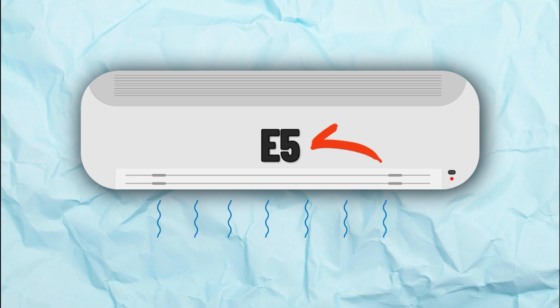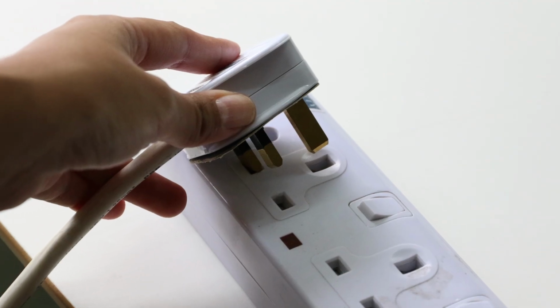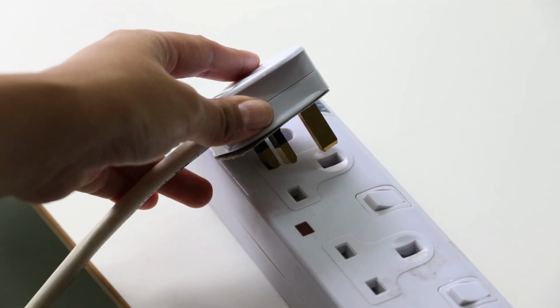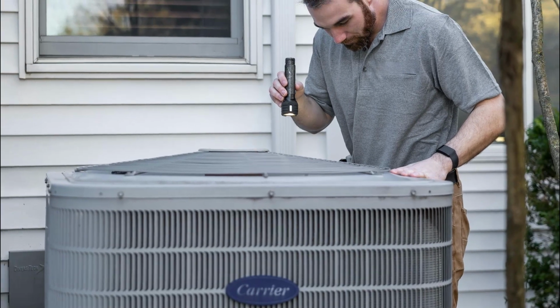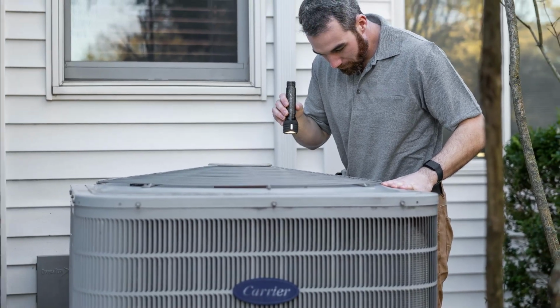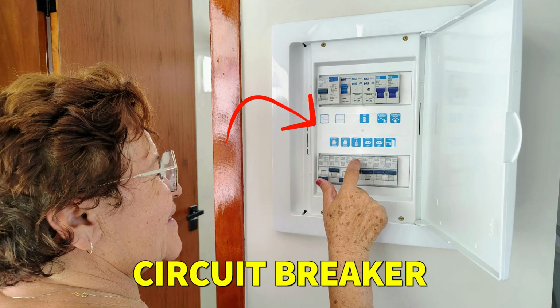But if E5 pops right back up, you're not looking at a glitch. You've either got unstable power at the outlet or an internal electrical fault. That's going to need professional attention. On Carrier units, E5 on the outdoor unit also points to voltage protection. For this, begin by checking your circuit breaker.